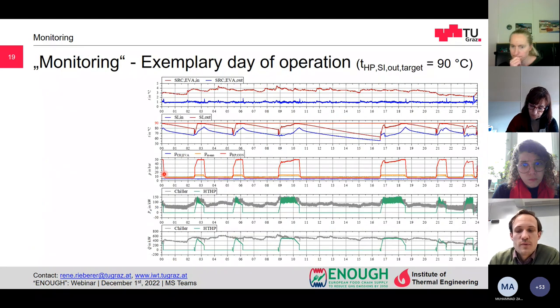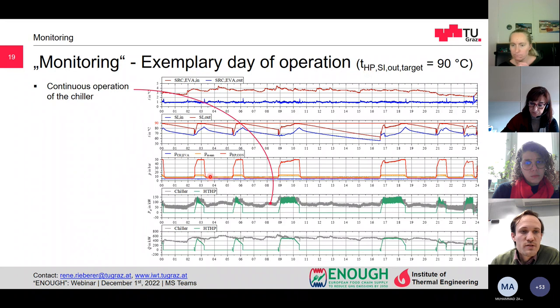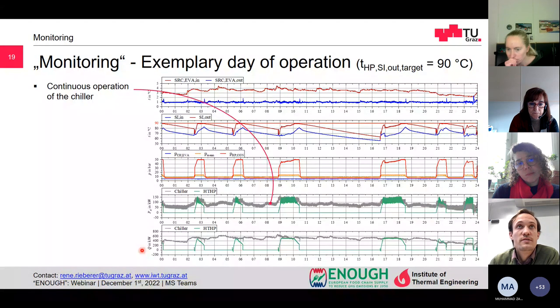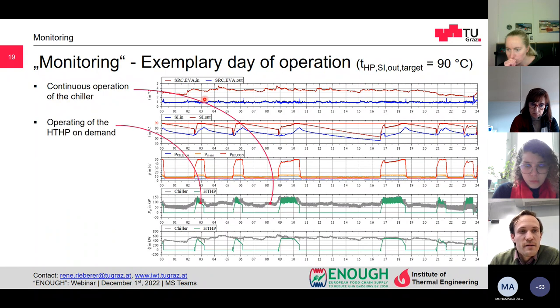To give you an example of a day of operation, I've taken one here with a target outlet temperature of 90 degrees Celsius, so a supply temperature of the heat pump of 90 degrees Celsius. What we can see here is that the chiller is operated the whole day with different power. And in the bottom figure, we can see the capacities, so the cooling capacity through the whole day. In the top figure, there is the heat source temperature, which is constant at around 1 degree Celsius. The high temperature heat pump was operated on demand, so if it is needed. This is the electrical power we can see here, and as well in the bottom figure, the capacity of the heat pump which was supplied to the cleaning in place system.